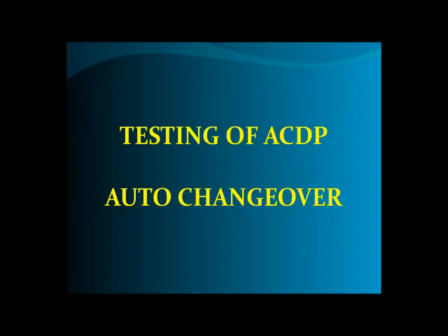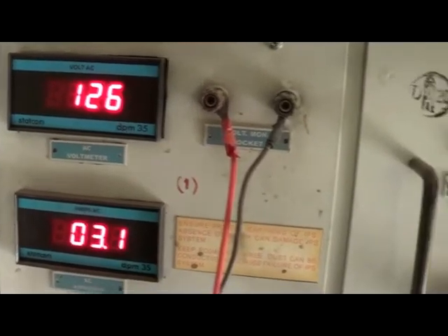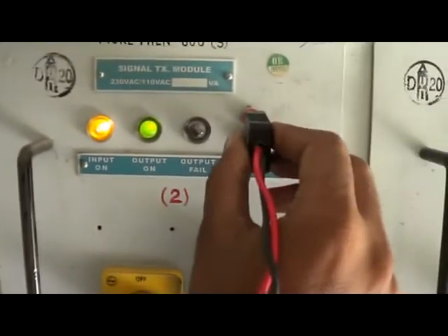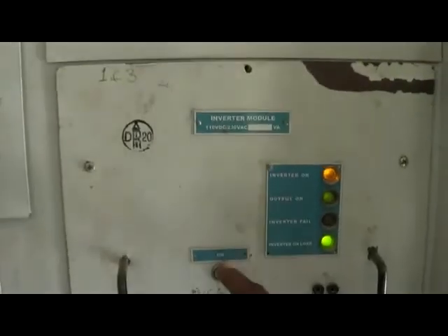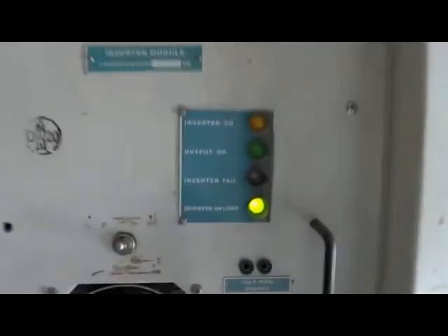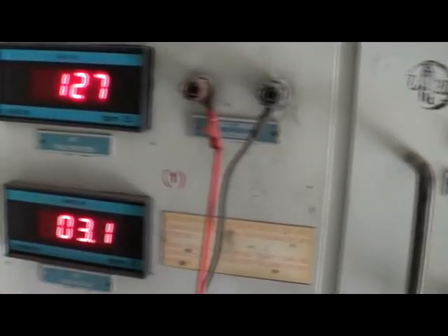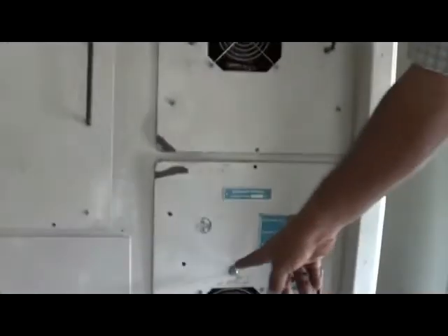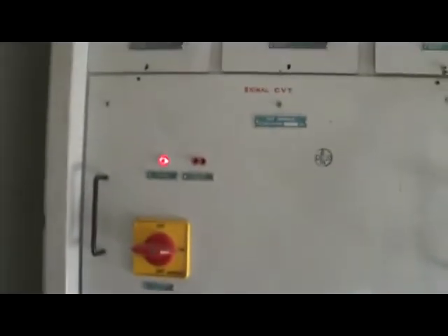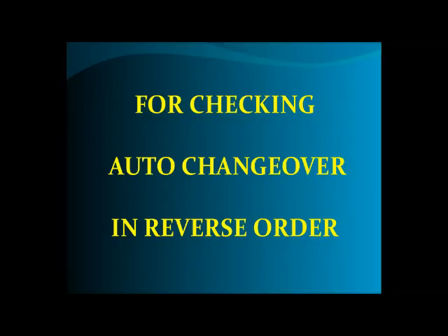Testing of ACDP auto changeover: Connect one of the signal transformer outputs to the digital voltmeter provided. Stop inverter 1 by pressing the stop button and check the load on inverter 2 LED. Check voltage on digital display. Now stop inverter 2; the voltage displayed indicates load on CVT.